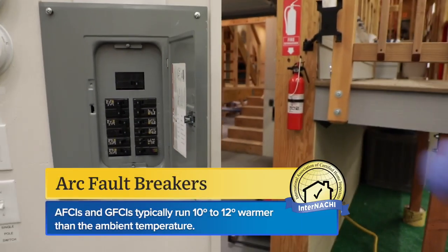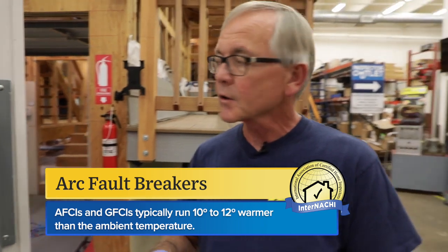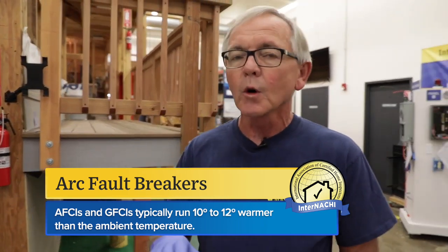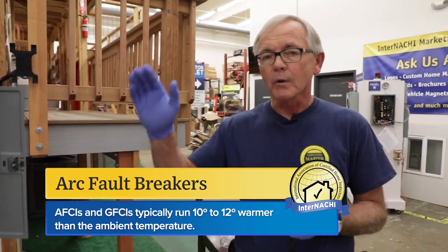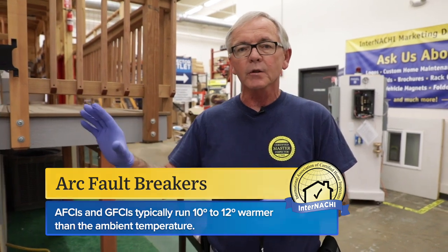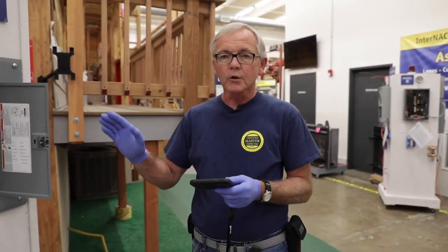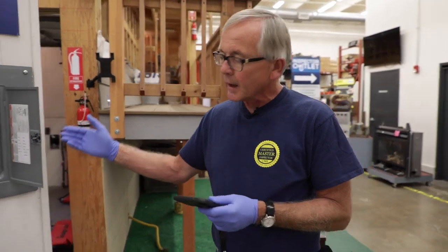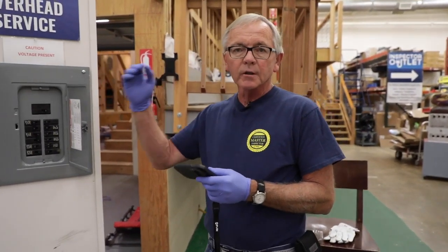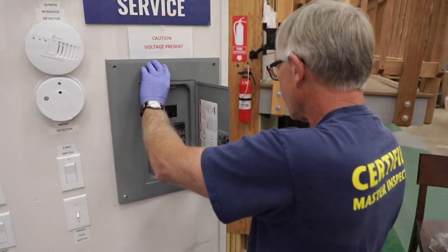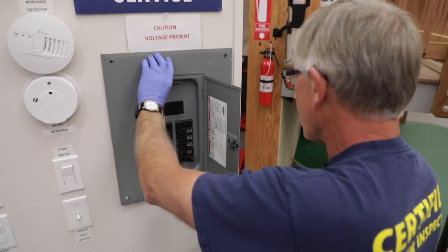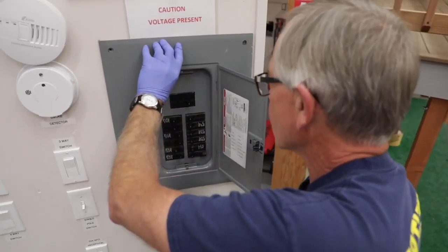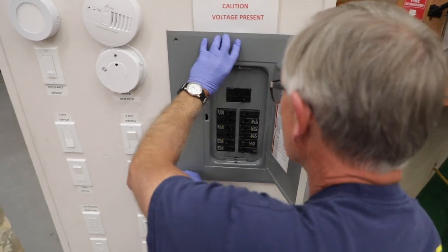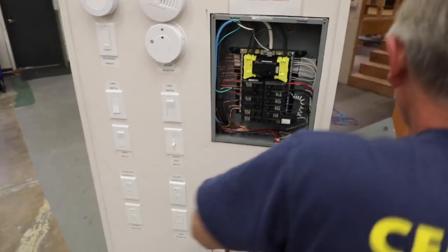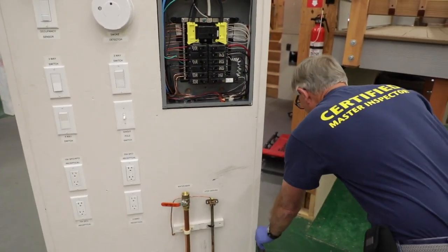Typically, arc fault breakers and GFCI breakers will operate at 10 to 12 degrees warmer than the surrounding ambient temperature of the rest of the breakers. Don't be concerned about that. That's just because they have internal electronics that are constantly monitoring those circuits. So I'm going to set my camera down, and I'm going to go ahead and pull off this panel cover. I've got these screws already loose. Okay, set that off to the side.